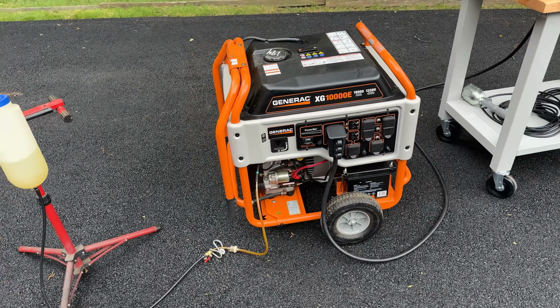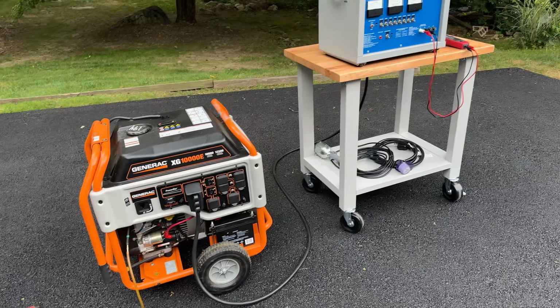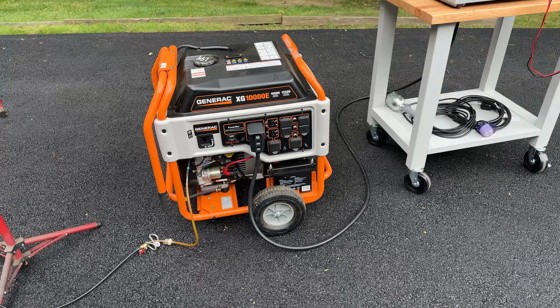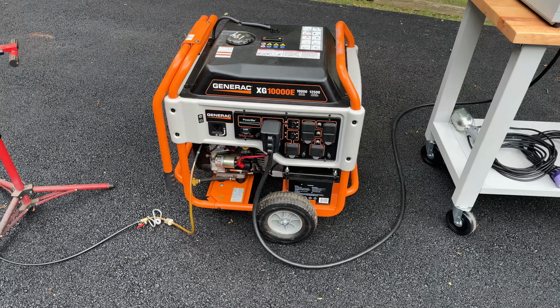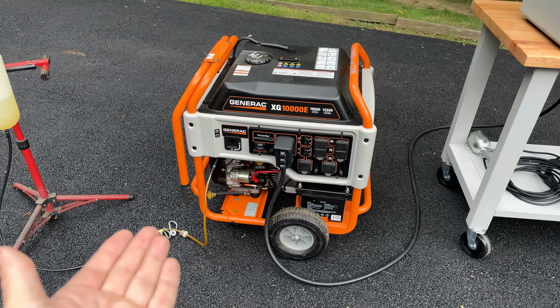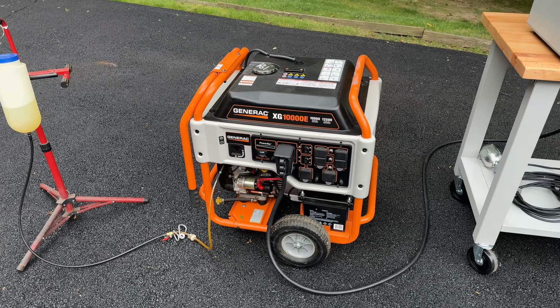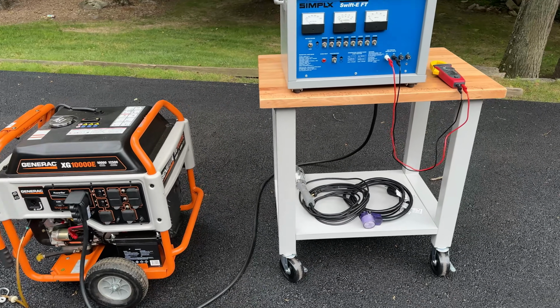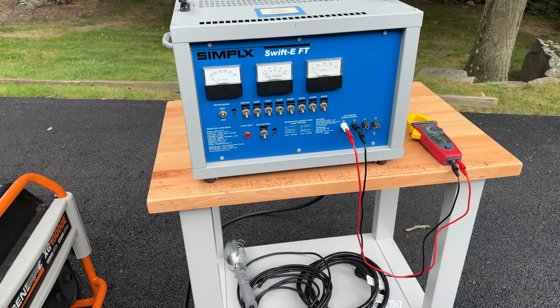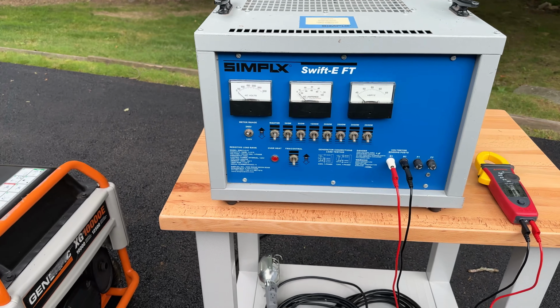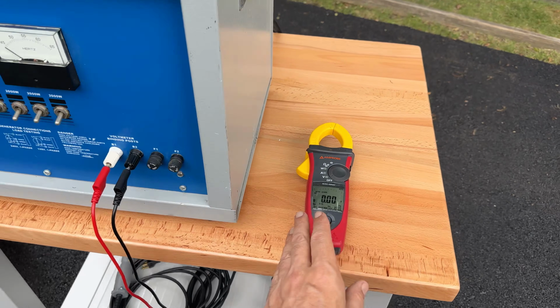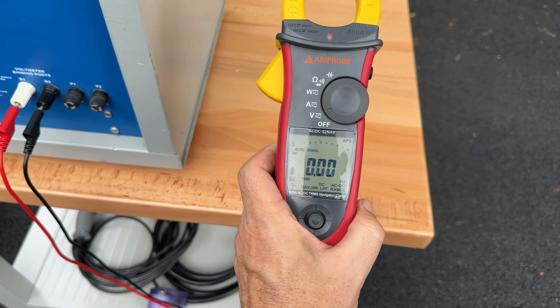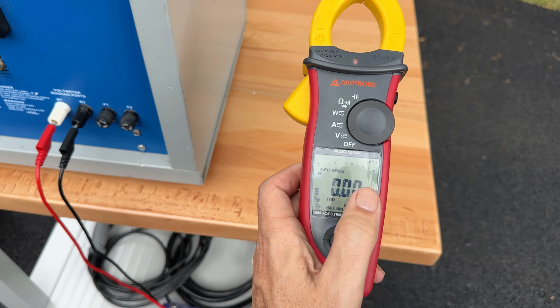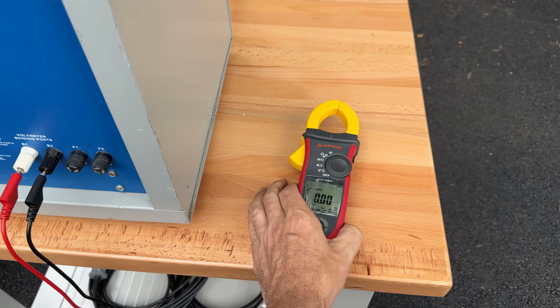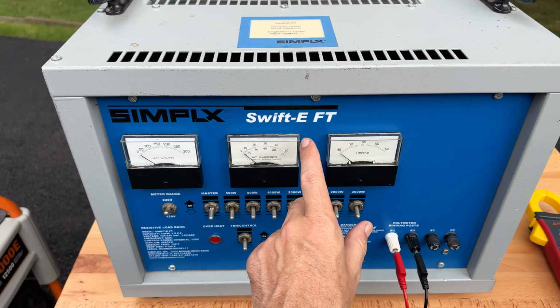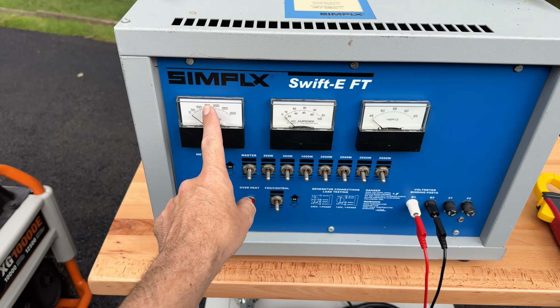All right, pretty much ready to go. We've got the load bank connected to the 50 amp, 240 volt plug. So the plan is to get it started, let the engine warm up, and put a half load on at 5,000 watts. We'll let it run like that for a bit, then double check the output. From here we can see the total harmonic distortion, the exact read on the voltage and the hertz, and compare that to what we see on here.